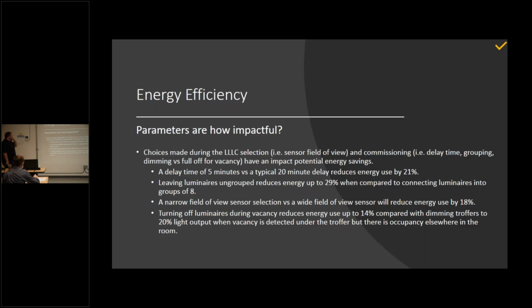So how actually impactful are these? The difference between a delay time of 5 minutes versus 20 minutes reduces energy use by 21%. So pretty significant. Leaving a luminaire ungrouped will reduce 29% compared to grouping them in groups of 8. So having the flexibility of a case-by-case basis increases your savings. The narrow field of view for a sensor versus the wide will reduce energy by 18%. Then turning off luminaires during vacancy will reduce energy up to 14% compared to dimming the lights to 20% when vacancy is not detected anymore.